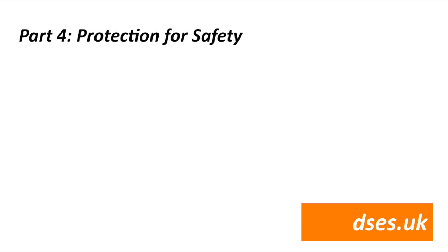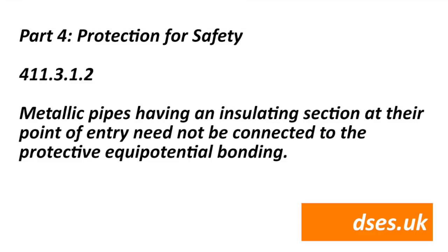There are no changes in Part 3, so we skip to Part 4 — Protection for Safety. There's an exciting change to Regulation 411.3.1.2: metallic pipes having an insulating section at their point of entry need not be connected to the protective equipotential bonding. At last — good riddance to water bonding, at least on those installations where the incoming service is plastic.